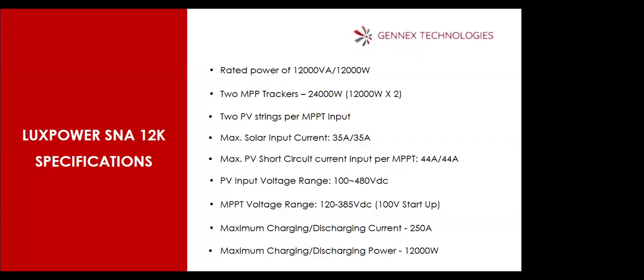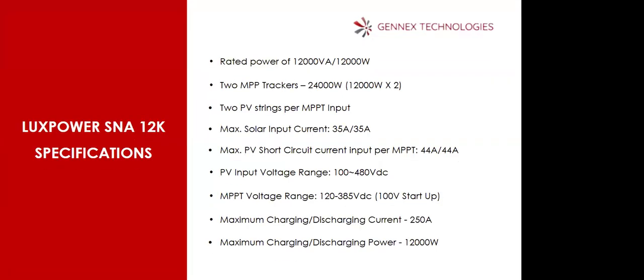Then the next one is the MPPT voltage range. That's the range of operation where it will begin to deliver power. And that range is between 120 volts and 385 volts DC. And in brackets, you can see the start-up voltage is 100. If the voltage is below 100, it's not going to see it, it's not going to wake up, it cannot do anything with it. It must go above 100. So if you're sizing, you don't size according to 100 volts alone. It has to go far beyond. The higher you go within the range, the better the performance of the MPPT.